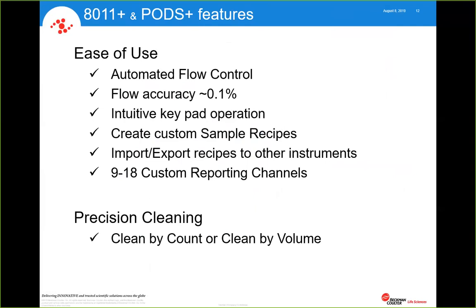And the precision cleaning, this is a nice tool for our customers. It's an automated walk-away cleaning routine where you can set it up to clean by a particular count on a channel size. Say, for instance, if 6 micron is a critical size for you, that you must have less than a certain amount of counts on that channel before you can consider the system clean. You simply set it up to say 6 micron, less than 10 counts, and you put in a cleaning solution, hit start, and it'll continue to flush until those counts get below that threshold, and then it'll stop.